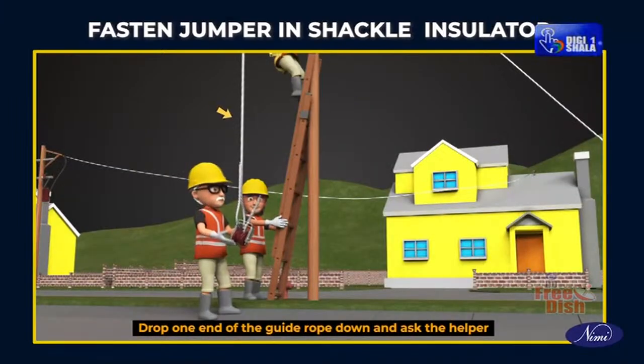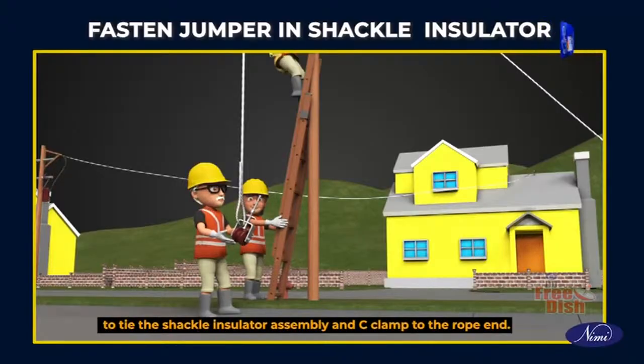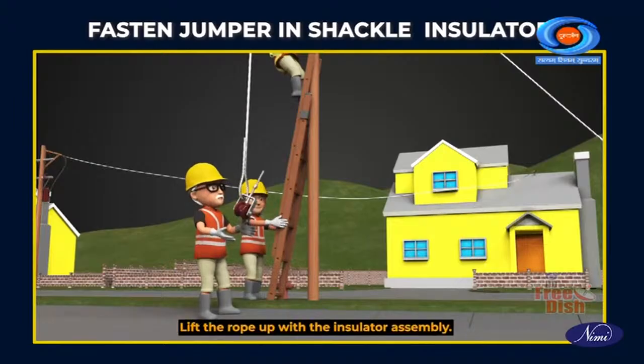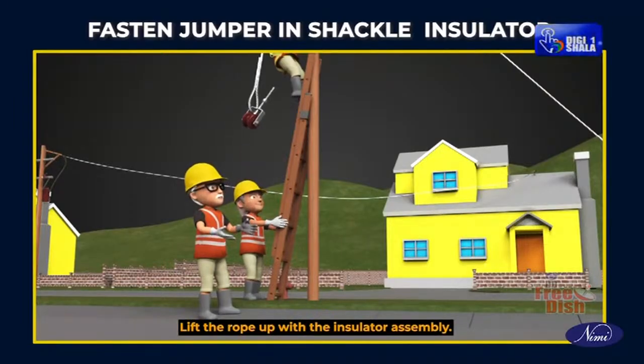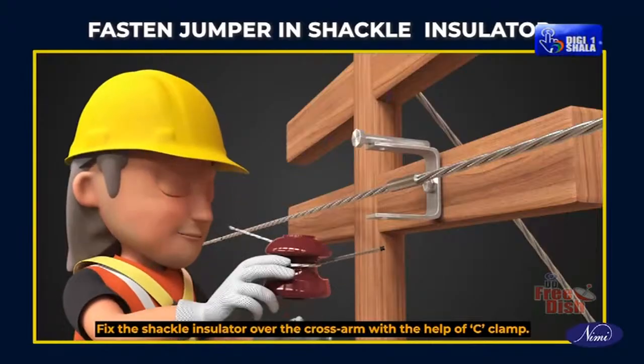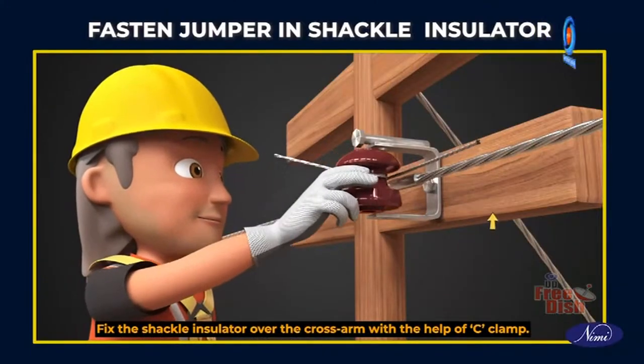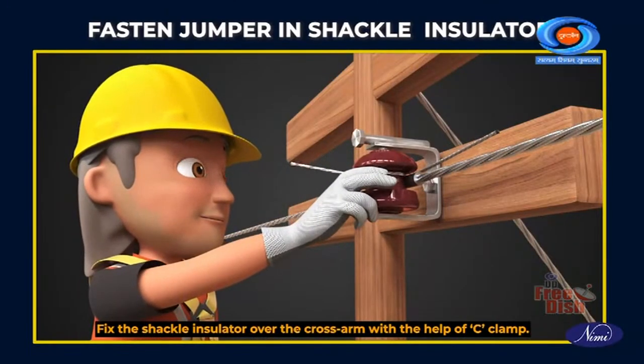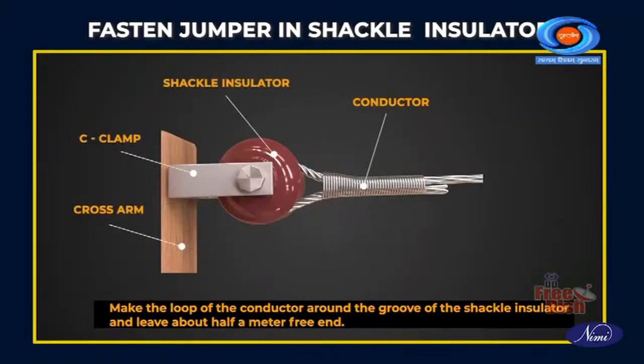Drop one end of the guide rope down and ask the helper to tie the shackle insulator assembly and C-clamp to the rope end. Lift the rope up with the insulator assembly. Fix the shackle insulator over the cross arm with the help of C-clamp. Make the loop of the conductor around the groove of the shackle insulator and leave about half a meter free end.